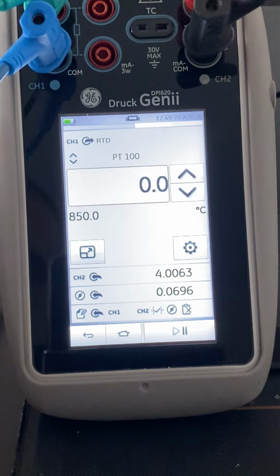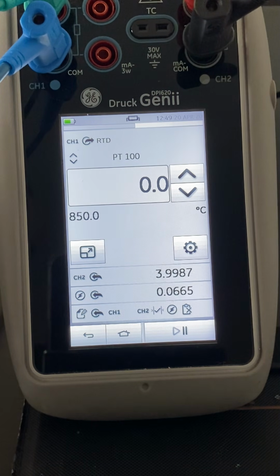We will be communicating with a Yokogawa YTA temperature transmitter. We did a calibration for that transmitter in the last video and we found some errors. So the purpose of this video now is to go and make the adjustment. The error was increasing as we are going up, which means we suspect there is a full-scale error in the transmitter. The transmitter setting is 0 to 100 degrees Celsius. The input is RTD-PT100, 2 wires.